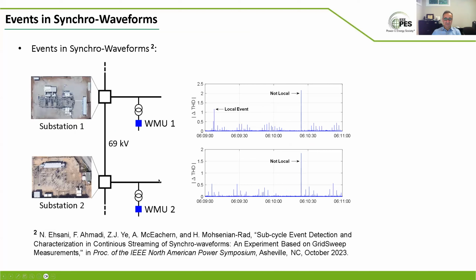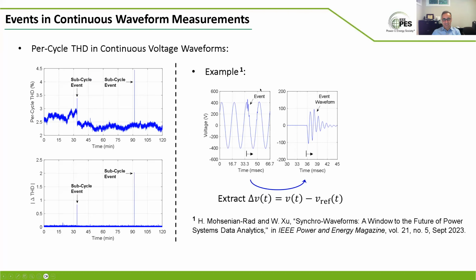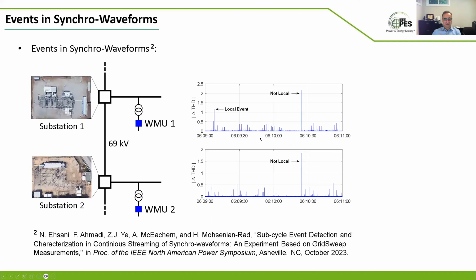Here's more of the same thing in a synchronized waveform environment. 2 waveform measurement units. These are low frequency waveform measurement units, just like these ones, only a few kilohertz, not megahertz ones. Let's call it a regular power quality meter. Connected to 2 69 kV terminals at 2 different substations. And if they are synchronized measurements, you can see something happened here that the equivalent of that didn't happen here or wasn't that size. So that's a local event.